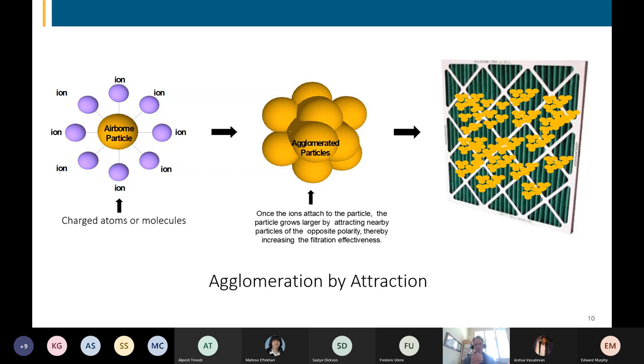The ionized atoms and molecules will go out into the air and make sure that the particles are charged oppositely because it's bipolar ionization, and then those particles will adhere, electrostatically attract to one another, and over time, clink, clink, clink, clink, they will become bigger. And because they have become bigger, we have increased their mass and their size. And because we have increased their mass and size, it is now easier for lower air exchanges or lower air velocities to help transport them through the air. And because they are bigger, it is also easier for filters to be able to extract them. But the important thing is, because they are bigger and transportable, we can now get them back to HVAC system mounted air filters that now can be efficient from the install, but effective in application because the particles actually get to them. This is nothing more than clean room technology.